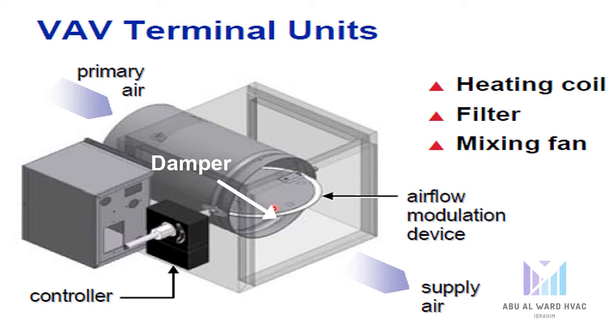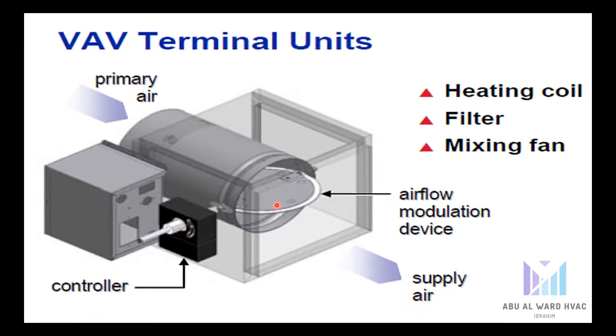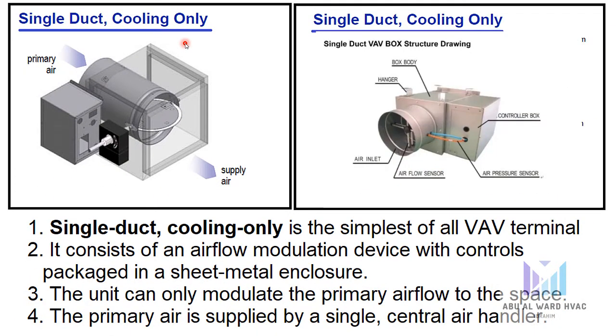It is very cost effective and flexible. Typically either a pneumatic or electric controller can be used to adjust the damper. The first configuration for VAV terminals is the single duct cooling only system. Single duct cooling only is the simplest of all VAV terminals — it consists of an airflow modulation device with controls, all packaged in a sheet metal enclosure.